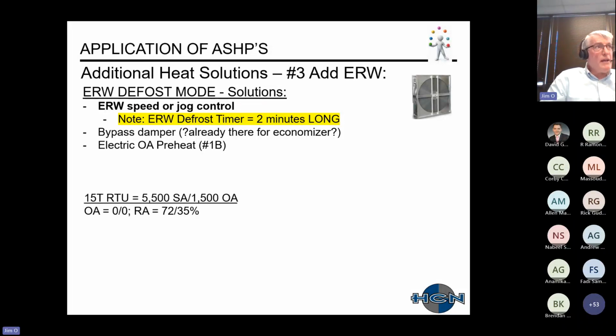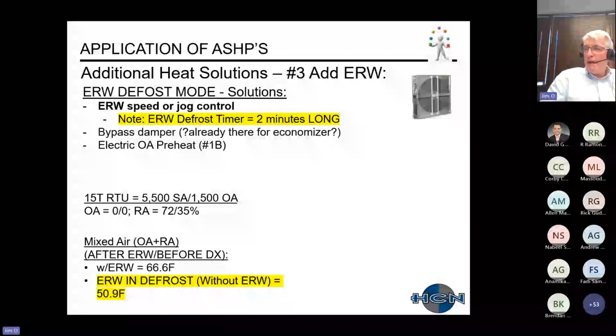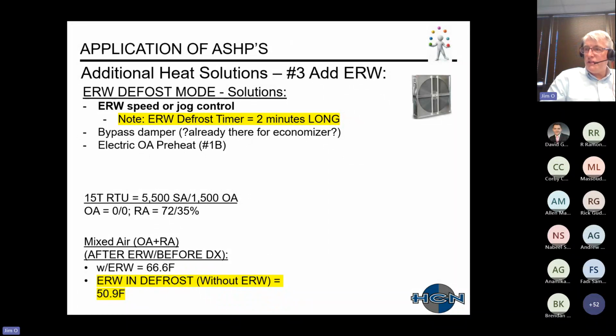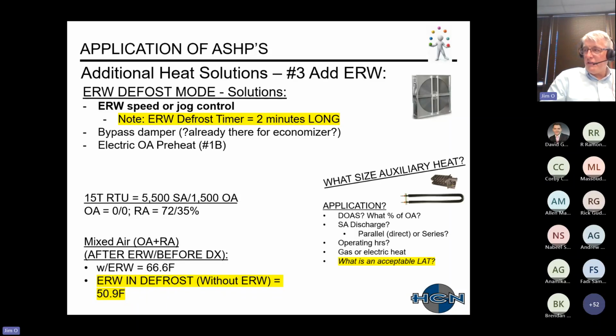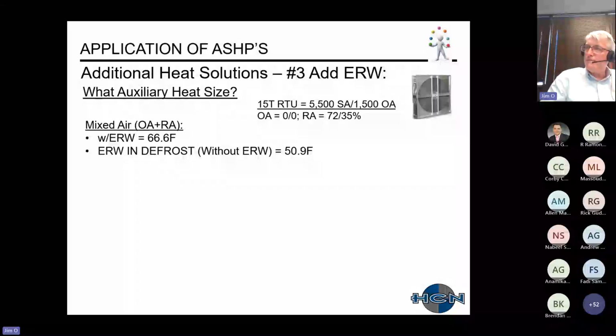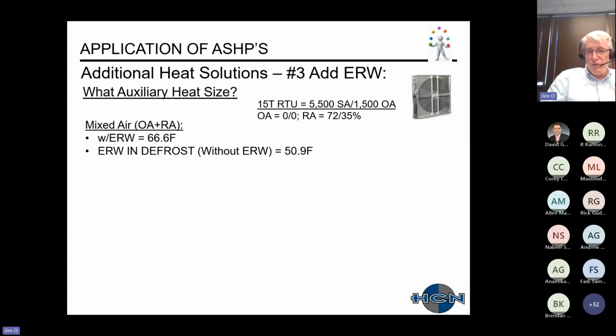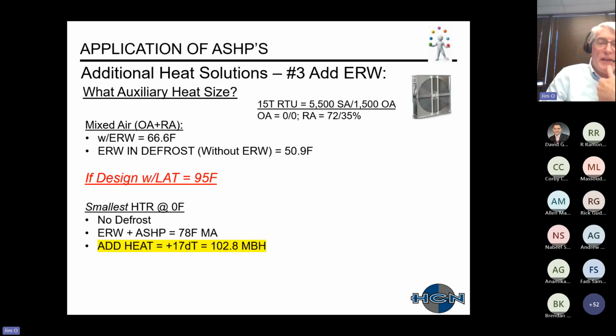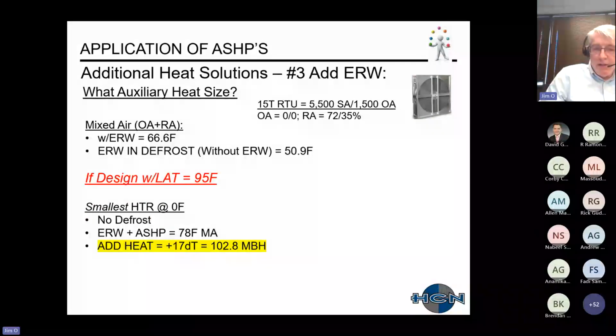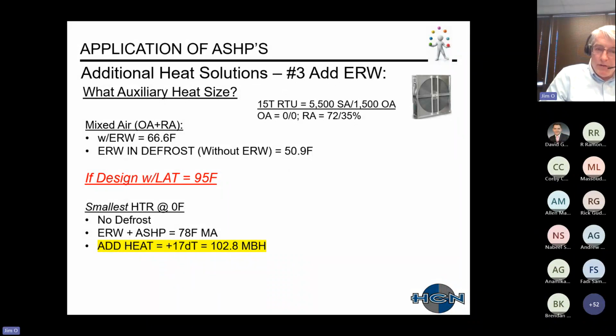So just looking at a 15-ton unit, we have these conditions. If you are comparing the mixed air temperature after the energy recovery or without the energy recovery, once again, you'd have to be concerned about what leaving air temperature you're looking for. So what auxiliary heat to use with our energy recovery wheel with these mixed air temperatures and conditions? If I'm designing for a 95-degree leaving air temperature, my smallest heater would be with nothing in defrost. We come up with an output of 102 MBH.